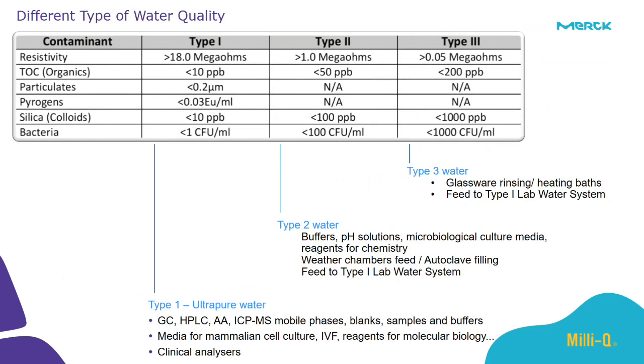In order to comply with the world standards norms for water, we have to define 3 types of water to be used inside our laboratory. Type 1 with resistivity higher than 18 mega ohm, type 2 with resistivity higher than 1 mega ohm, type 3 with resistivity higher than 0.05 mega ohm. Due to the cost, we need to estimate exactly what our consumption would be: type 1 water for critical applications only, type 2 for general applications like buffers, pH solutions, microbiological culture media, and type 3 for glassware rinsing, heating baths, and feed to type 1 lab water systems.